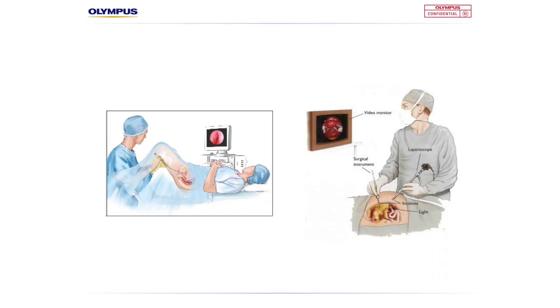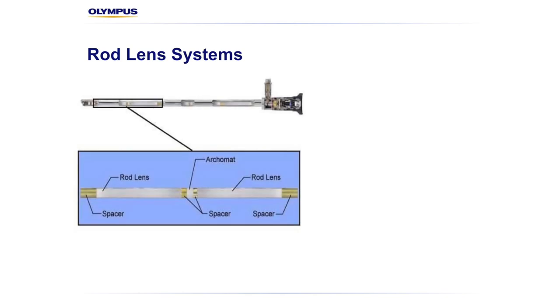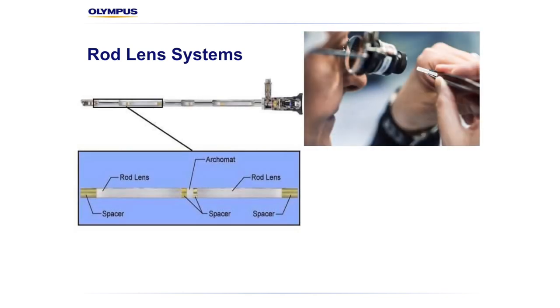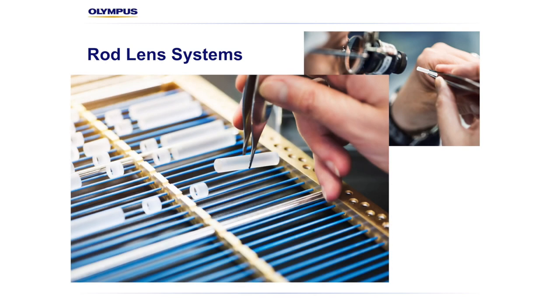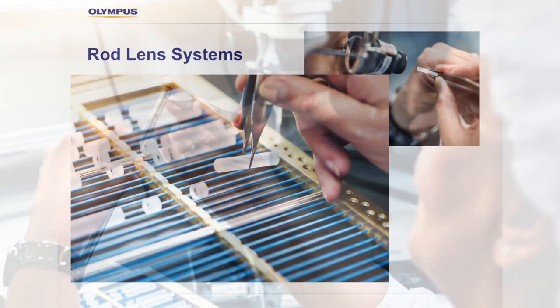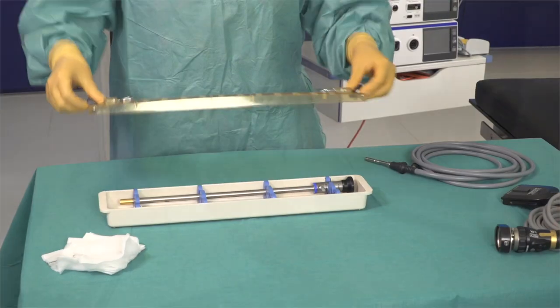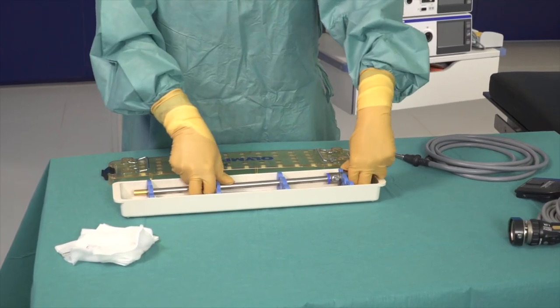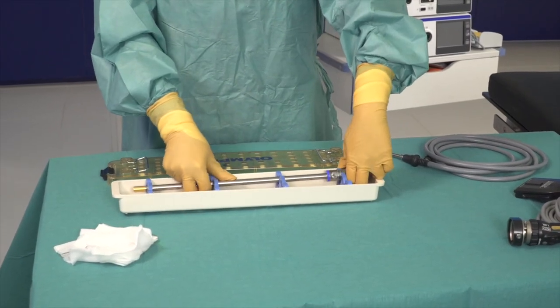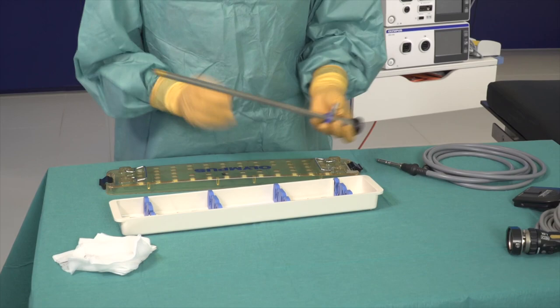Telescopes allow us to carry the surgical scene outside of its cavity and project it onto an ergonomically positioned surgical monitor. To maintain a high quality image where no detail is lost, telescopes must be made from specialised glass lenses and fibre optics, which means they need careful handling. Furthermore, the lens of the telescope is our surgical eye and it must be kept clean at all times.